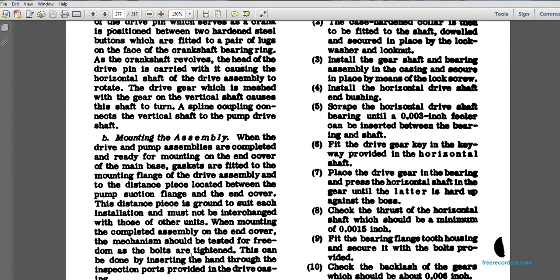Mounting the assembly. When the drive and pump assemblies are completed, they are ready for mounting on the end of the main base. Gaskets are fitted to the mounting flange of the drive assembly to the distance piece located between the pump suction flange and the end of the cover. The distance piece is ground to suit the installation and must not be interchanged with those of other units.